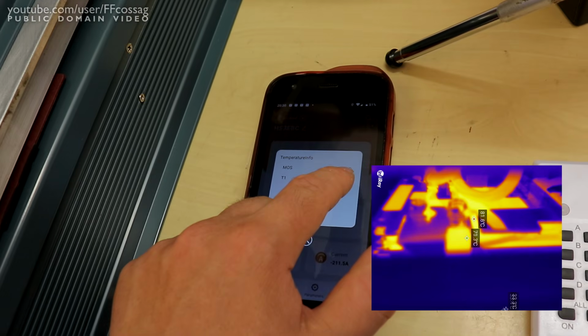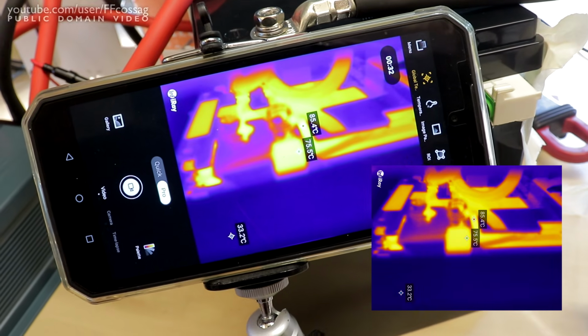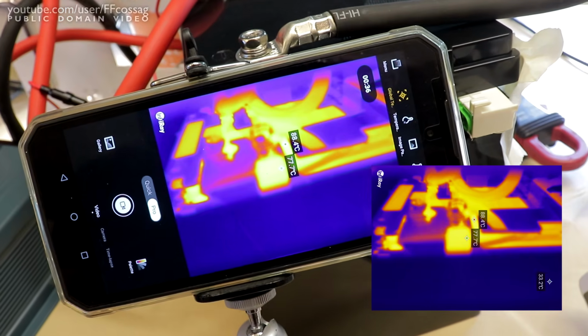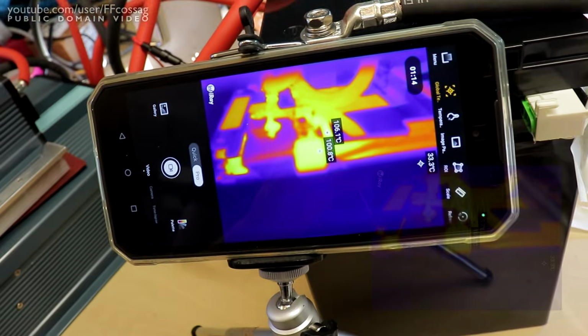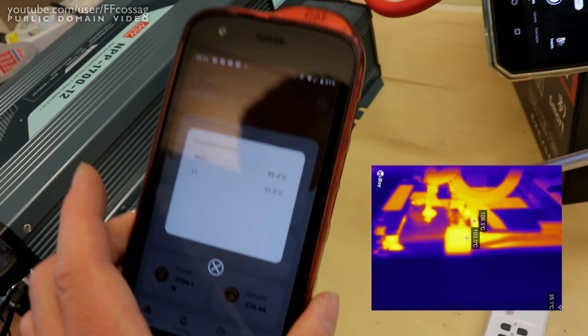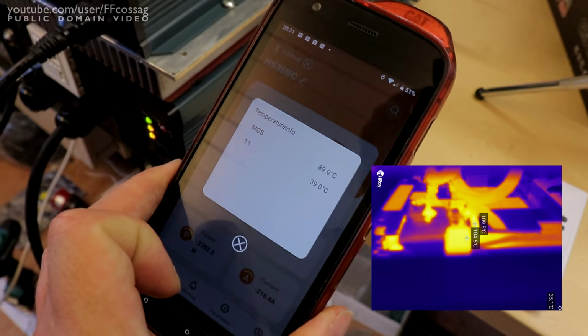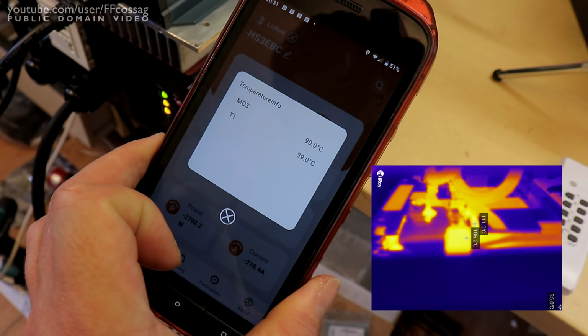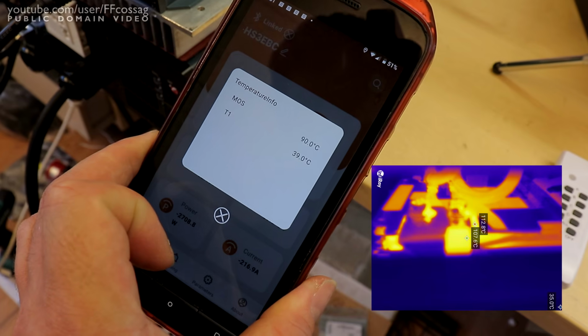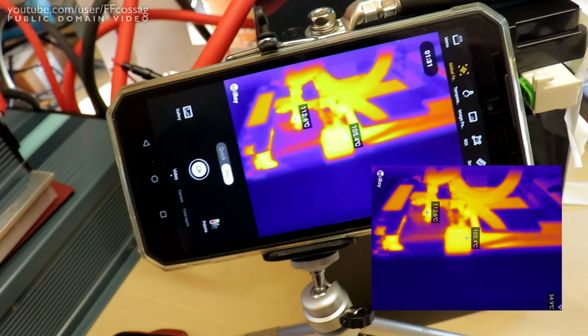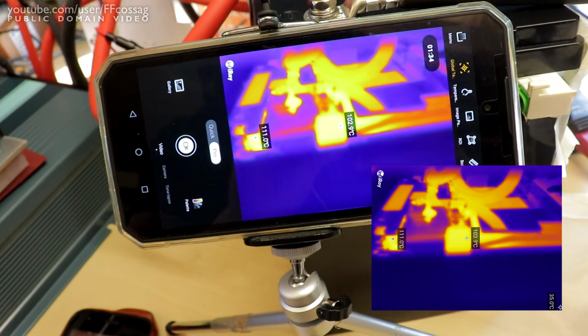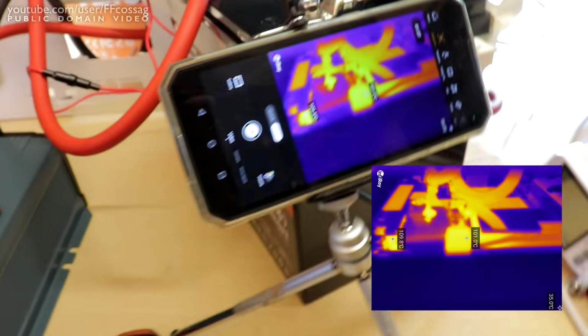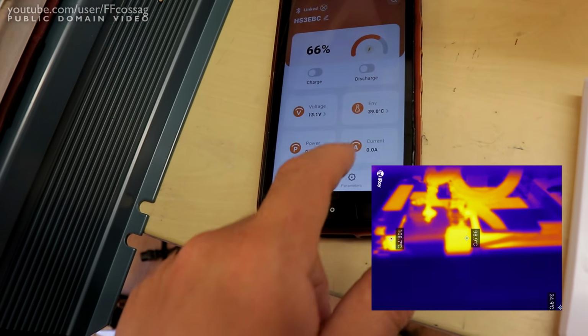So we're already quite preheated, 77 on the transistors, and at 200 amps it's not running as excessively hot on the bus bar. 80 degrees. 90. 85 degrees on MOSFETs. 96, 97. So we're going to trip out in just a second here. 89, 90, and it trips. Okay, so that's definitely hot, but not Battleborn tier hot, not Chernobyl hot.